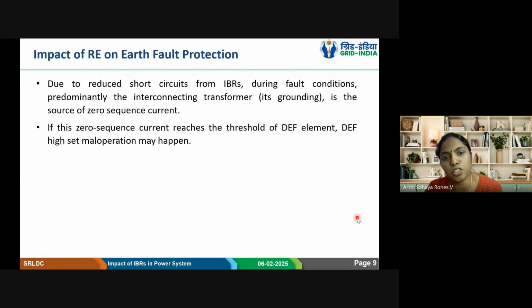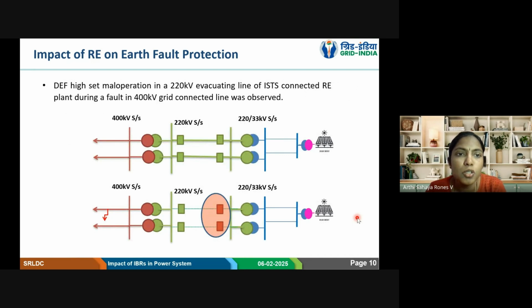So when the zero sequence current reaches the threshold of the DEF element, the directional earth fault component, this kind of maloperation can happen. So to show this, I have some case study. So let us take first case in which there is a fault in the 400 kV system. That's a 400 kV grid connected system. There is a fault. And here we are having solar at 33 kV. It is getting connected. And this is 220 by 33 kV transformation.